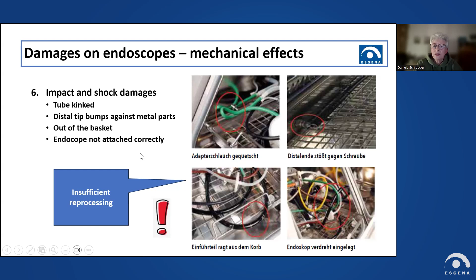Or the special situation, a leaky endoscope, where water is in the optical system, which then needs to go for repair, with high repair costs. To avoid black spots, not due to damages but due to other reasons, I would like to motivate you not to leave the endoscope in the AER overnight or over the weekend. Please take it out immediately after the cycle is finished. This is a wet area, and due to diffusion, the moisture will go in, and then we will also find black spots in the screen.